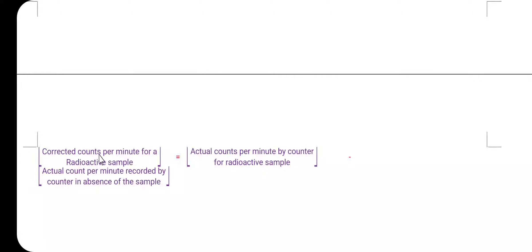Measured counts are always corrected for background counts. The corrected counts per minute for a radioactive sample equals the actual counts per minute recorded by the counter for the radioactive sample minus the actual counts per minute recorded in the absence of the sample. Subtracting these two gives the corrected counts per minute. This concludes the discussion on the Geiger-Muller counter.